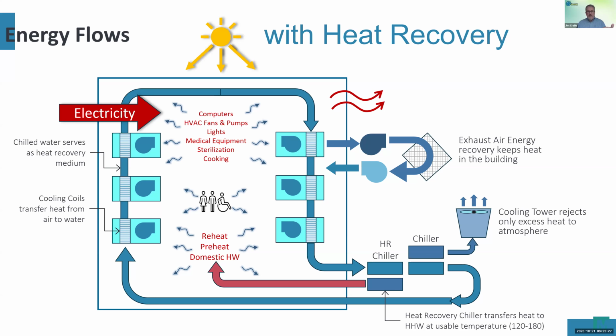we can reconvert that heat to a usable temperature, like 120 or 130 degrees. Some older systems need higher temperatures, which we can also achieve with heat pumps, though less efficiently. Through this heat recovery process, we recapture that heat, keep it in the building, reuse it, and throw less away, so we don't have to burn gas to make the heat our buildings need.